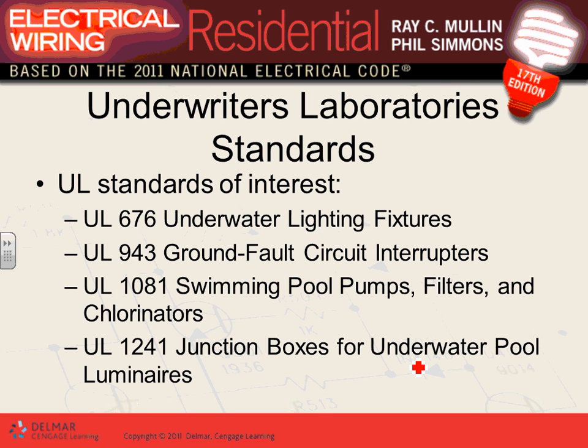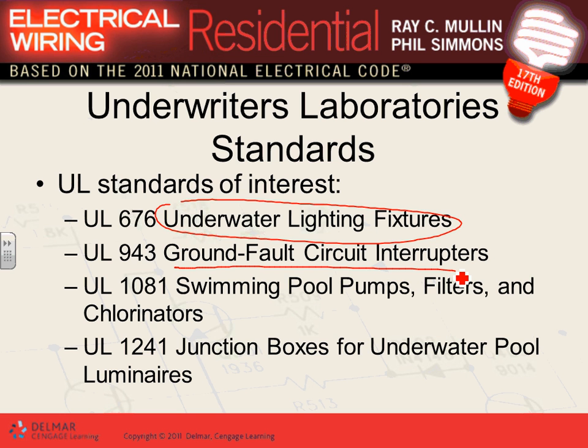Okay, this is just a couple of rules and regulations, UL standards, guys, for a swimming pool. Underwater lighting systems have their own regulations, guys. A lot of these swimming pool and spa lights are typically low voltage contact limits. They run them at 30 volts or less. They are ungrounded systems, so they're safe, basically. There is a lot of regulation for ground fault protection required for all the receptacles, 15, 20, and 30 amp, within 20 feet of a swimming pool. You have to put them on GFCI. Swimming pool pumps, filters, and so forth: the pumps themselves, if they're single phase, 120 through 240, guys, have to be GFCI'd too.